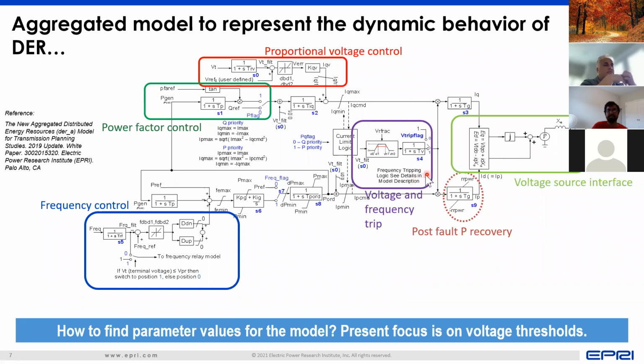And the reason to focus on that is because the majority of the DER that are located in a lot of feeders today don't really have this kind of behavior where they provide frequency control. They don't have the kind of behavior where they may provide proportional voltage control, but instead they are pretty much constant active power devices. If you consider most of them being PV, then depending upon how much sun is shining, in terms of the radiance from the sun, they will generate a level of active power, which will be directly injected into the network. But if the transmission voltage drops, or if the transmission voltage changes, they will start to trip.